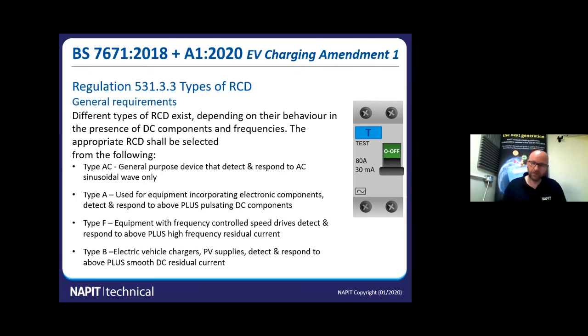Okay. And sorry, Paul, just to mention something very briefly, for the guys out there, I did a little viewing of YouTube over the last while to see what was out there, and I noticed some charge points that don't have DC leakage monitoring, where the installers are fitting a type A RCD. That does not meet the regulations. So be clear, guys, on the requirements and what the charge point has, along with ensuring you're using the right RCD or RCBO.